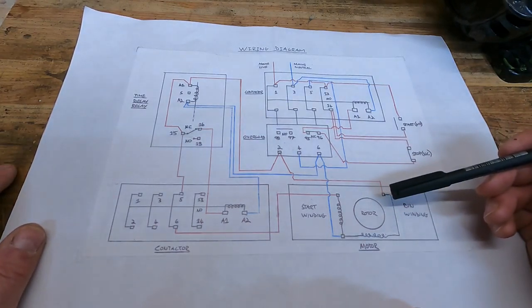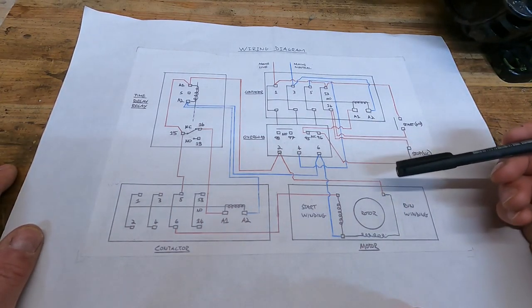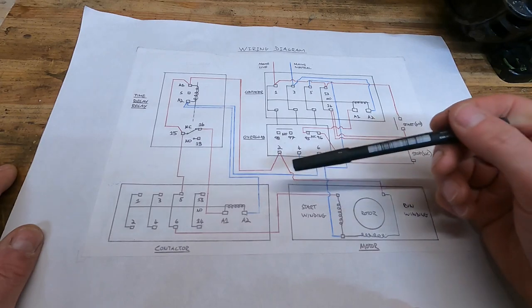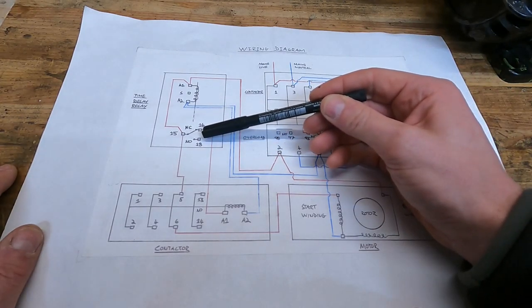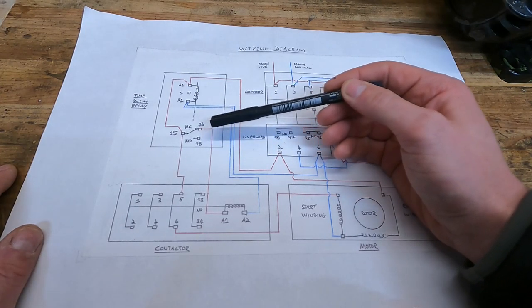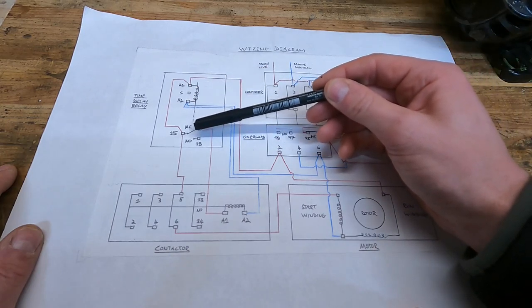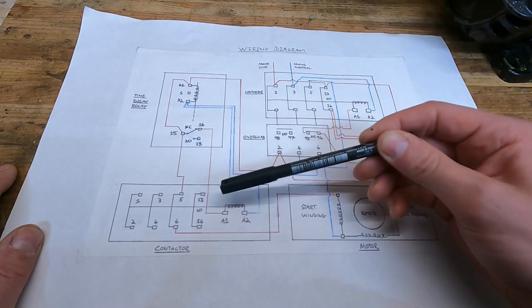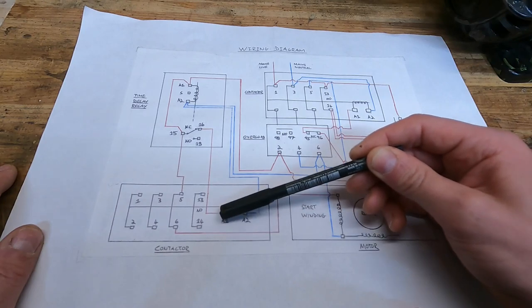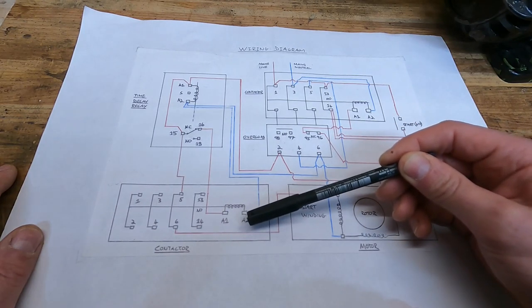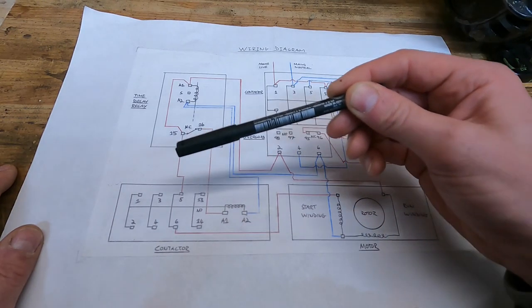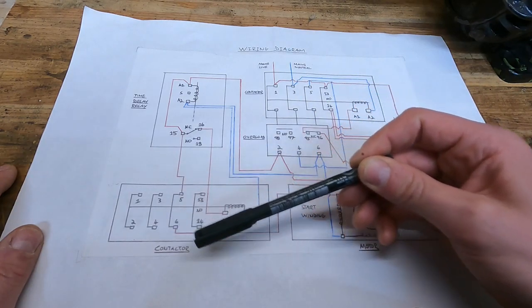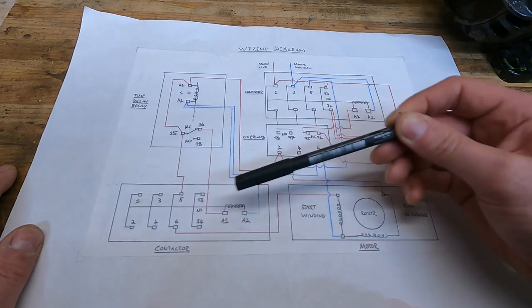So the way we're going to get around that is, instead of the start winding load going through the contacts on the time delay relay like we had before, the time delay relay is going to switch on and off another coil in another contactor. Then that contactor will actually switch the load of the start winding, and that contactor will have a higher spec that's designed for switching these sorts of inductive loads.